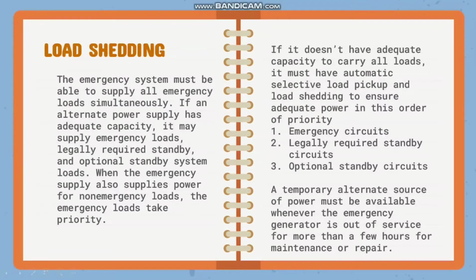So dito, nabanggit na to kanina yung sa level of importance niya. So proceed na tayo. Next, a temporary alternate source of power must be available whenever the emergency generator is out of service for more than a few hours for maintenance or repair. So kapag under maintenance or repair ang emergency generator na nagsusupply sa emergency loads, dapat merong standby alternate source.